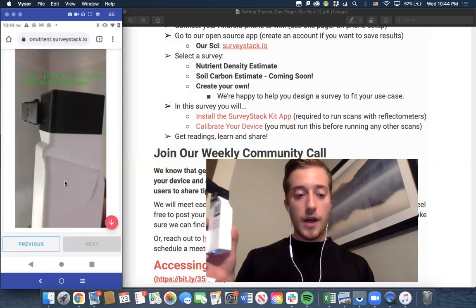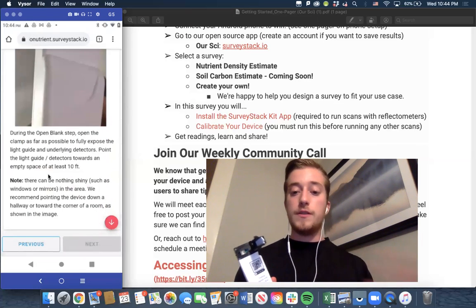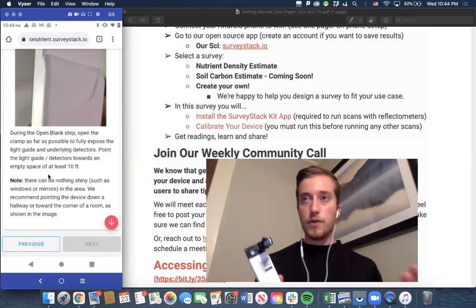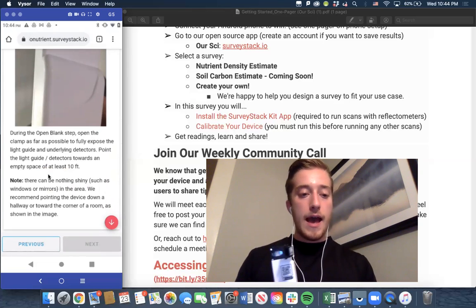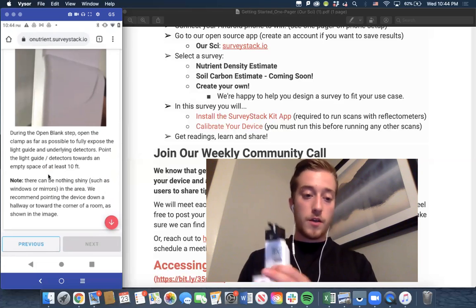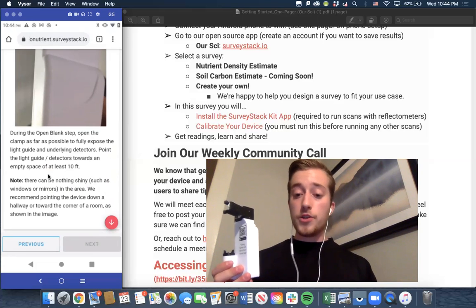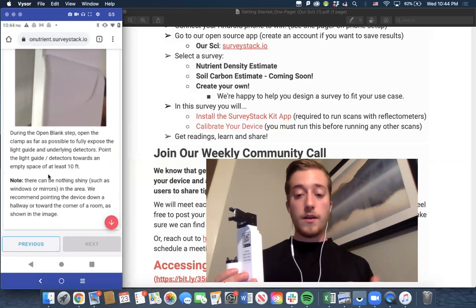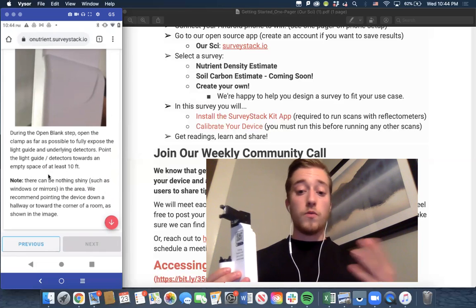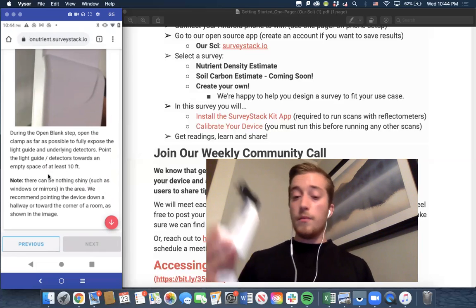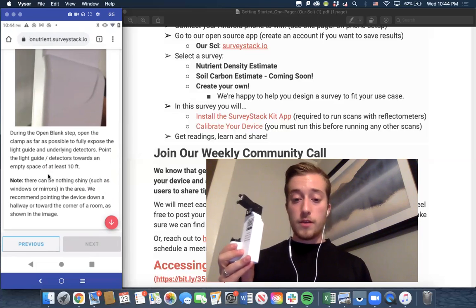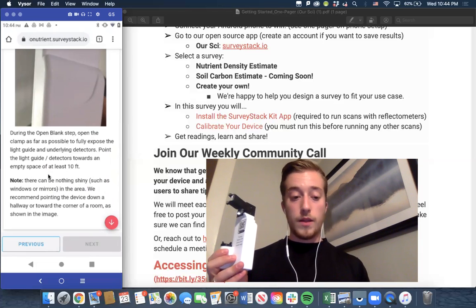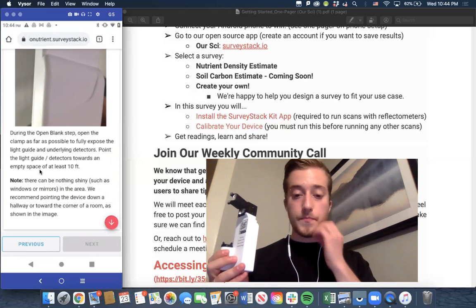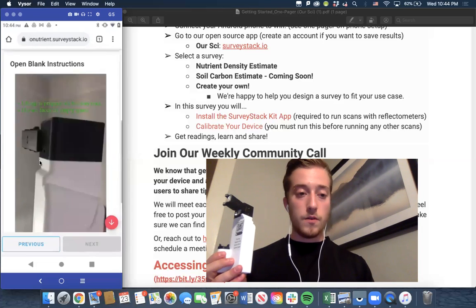And then you're just going to shine. The open blank is creating your 0 value, like the least reflective thing you can find for your range calibration, right? So for this, you want nothing shiny. You don't want any windows in the way, no mirrors, no light sources. I am shining my reflectometer into the corner of a room with nothing particularly distracting for the LEDs in the way.